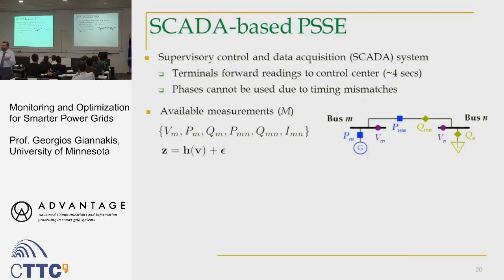This is among the advantages that the PMUs, the phasor measurement units, bring to the table. They receive signals from GPS stamps, so they know exactly the phase. Traditional meters measure only voltage amplitude, or active or reactive power, or power over a line, or current — remember, the calligraphic letter is the complex quantity, the Roman is the amplitude — so no phases are measured.